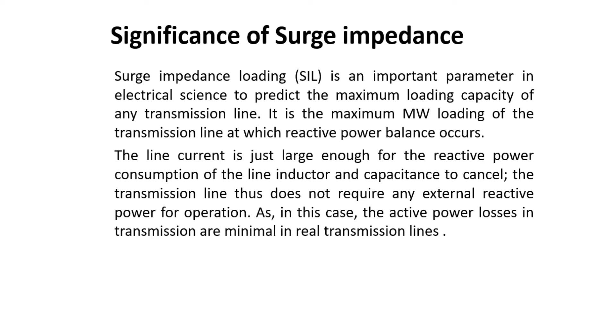Now we have to see the effect of surge impedance loading on the line. You will see in the observation table that we connect different loads, from R1 to R7, and at one value of the load resistance, that is the value equal to the surge impedance of our line, we have maximum power transfer, because the reactive power consumption at that point is minimum.